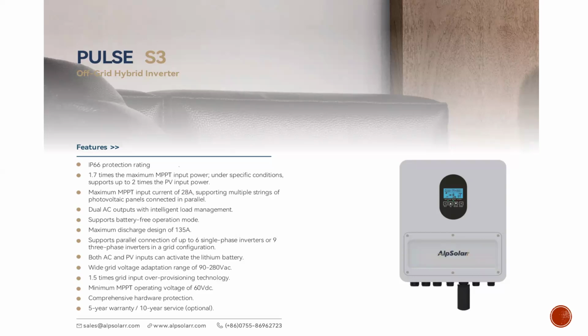For some, there are other appliances that they do not need all the time. They put such appliances on load two, and then they can set the smart load against the SOC of the battery. Let's say you can say once my battery is 80%, all the loads on smart load can come on. And when it is, let's say, 40%, all the loads can go down. All of this is just to help you to intelligently manage your load and give more priority to your critical load, right? And of course, it supports battery-free operation mode. This inverter can take input from the grid and works independent of the battery. It can take input from the panels and work independent of the battery. So without battery, with the input from the PV, it's working fine. With input from the grid, it's working fine. And of course, it works with your battery as well.